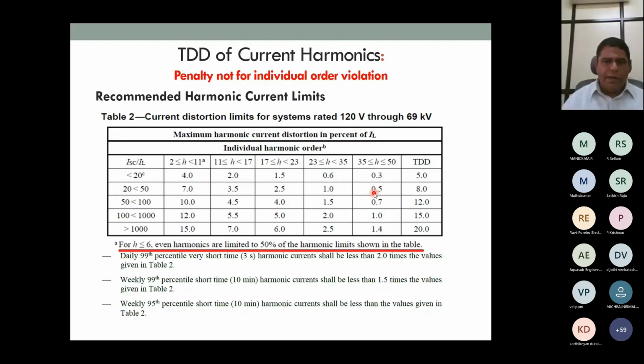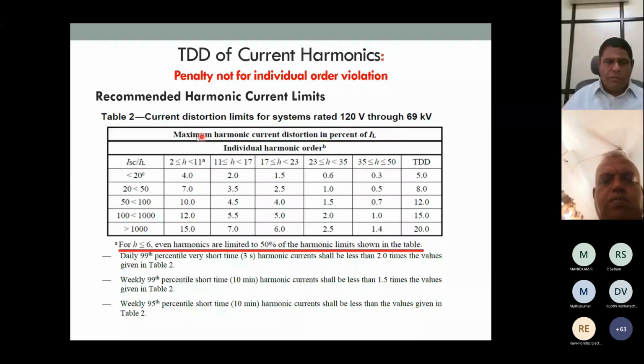So this is the TDD table. I have taken only up to 69 kV. Above 69 kV, there is something called table 3. People have to refer to table 3 for the current distortion limits. What I mentioned here is penalty not for individual orders. So these are the limits for individual orders. Say, for example, between 2 and 11, so 2, 3, 4, 5, 6 till the 10th harmonic, this will be the limit. From the 11th harmonic to 16th, this will be the limit.